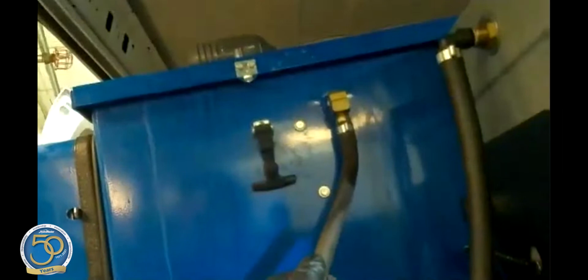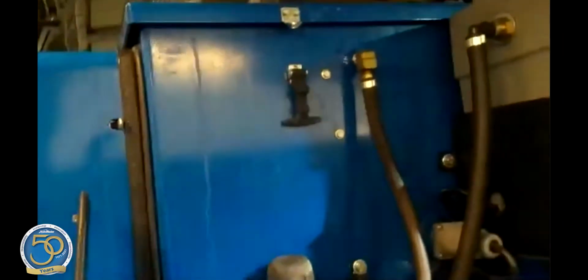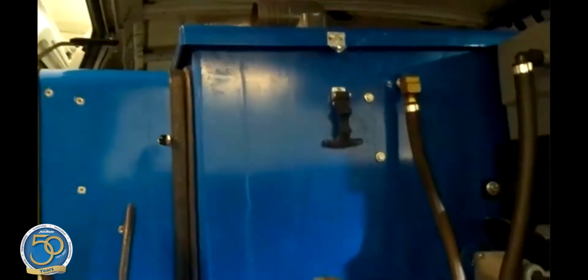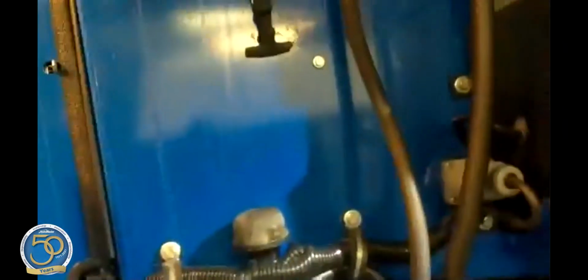So again, on your CDS, if you are having symptoms of your waste tank filling up too fast or faster than you're used to, and you're not building heat like you normally do, then the first thing you want to check is if this thermal valve is dumping water into your waste tank all the time. You can lift up the tank and look on the other side of this fitting, and if it's just constantly dumping in there, then that thermal valve needs to be replaced. Another way of checking that to make sure it's operating properly, because it is supposed to dump in there at 165 degrees, is you would put a thermometer inside the water box and watch that temperature rise.